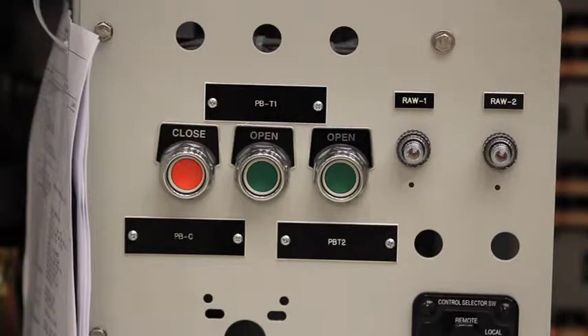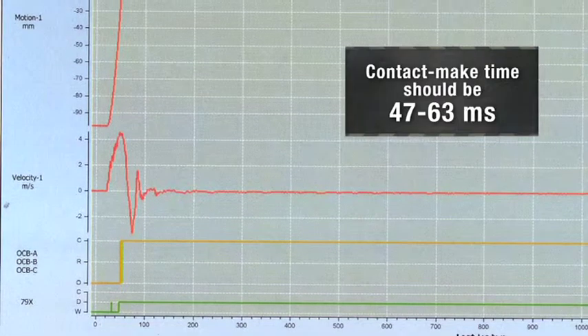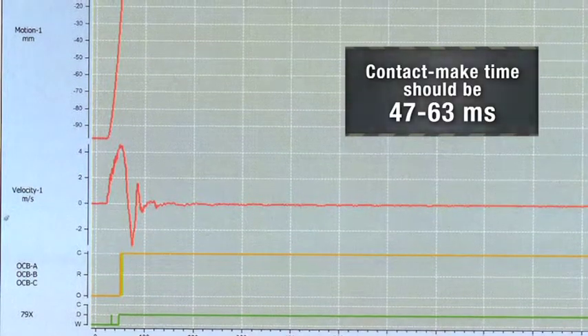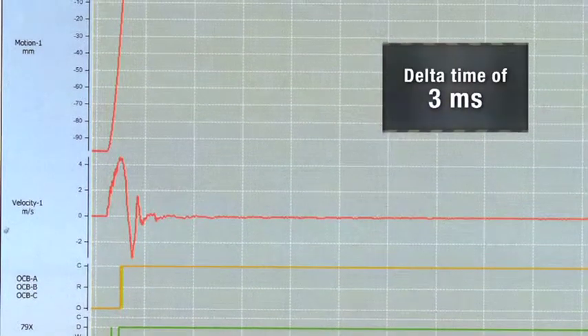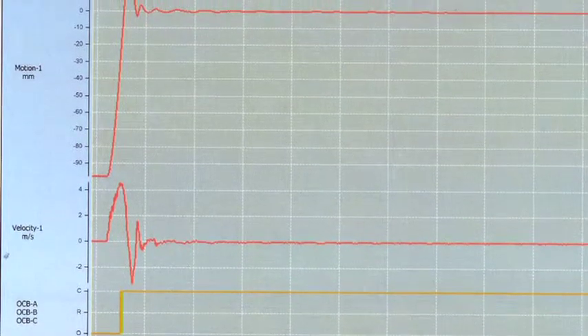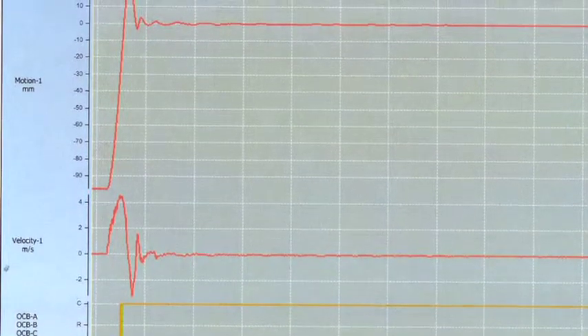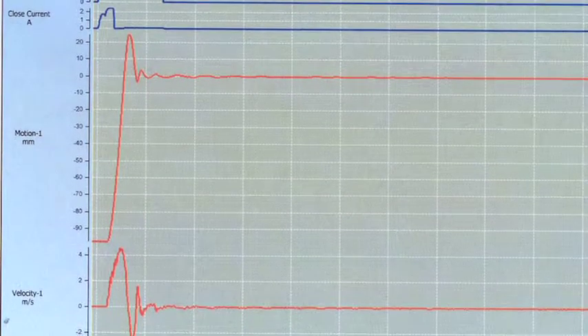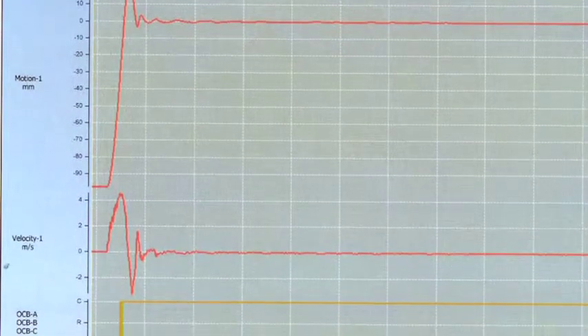Perform one close operation and measure contact make time. Contact make time should be 47 to 63 milliseconds. Delta time of 3 milliseconds should be included. As with the open operation, arc rings touching the stationary contacts may result in premature intermittent indication of contact make up to 5 milliseconds before actual contact make. This too is normal and no cause for concern.